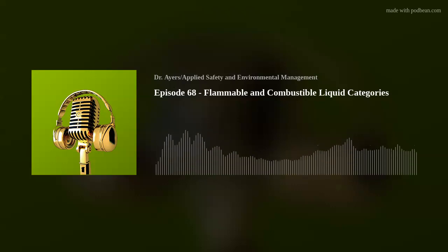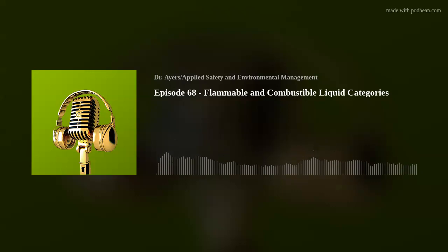So in today's episode, it's mainly found at 29 CFR 1910.106. The title is Flammable Liquids. And so basically, when we sit down and talk about flammable, there's going to be two categories, even though it's overall known as flammable. It's flammable and combustible liquids. So let's cover a couple of definitions.